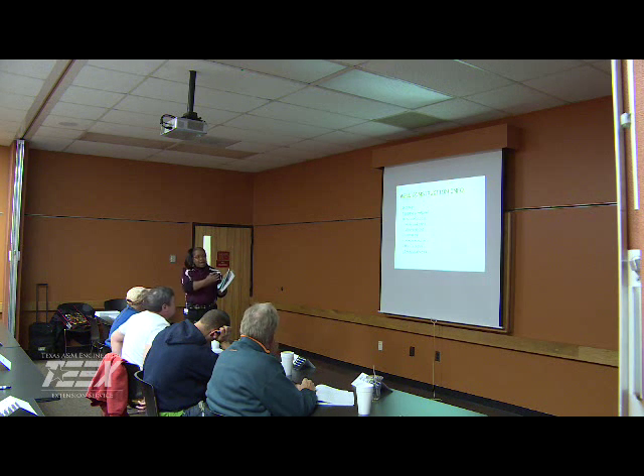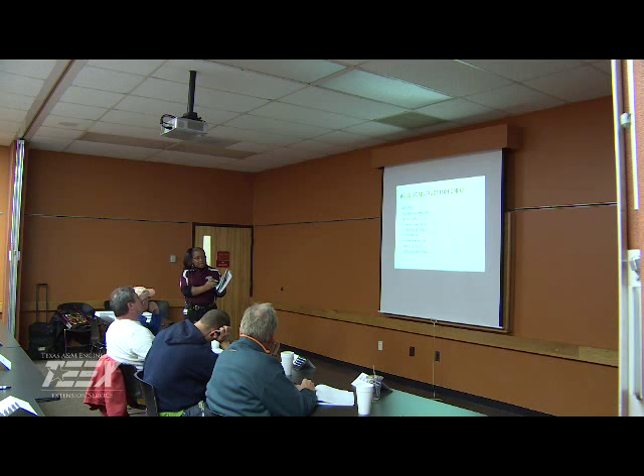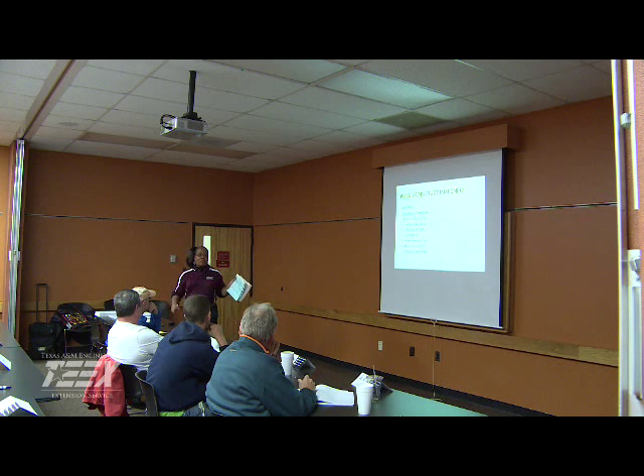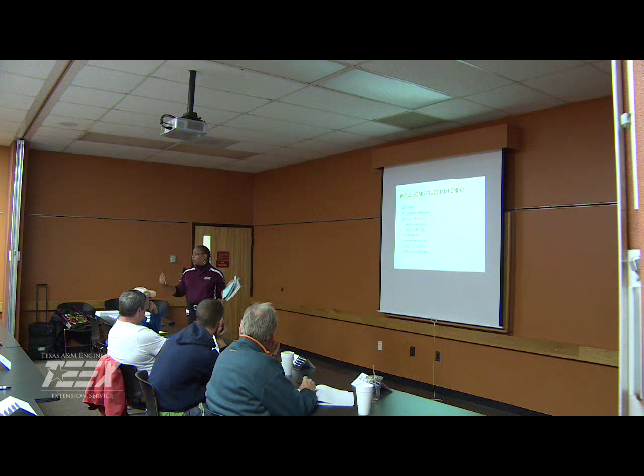Those are constant. So once I have that number, I'm going to multiply those results, which would be BHP, times 0.746. That is the conversion to kilowatts. Once I've converted it to kilowatts, how many hours in a day? 24. And that will give me kilowatt hours. So this converts horsepower to kilowatts, times 24 for kilowatt hours. And I can actually do an analysis of my pump, how much it is going to cost for a year, for a month, for operations, as long as it's within certain efficiency.